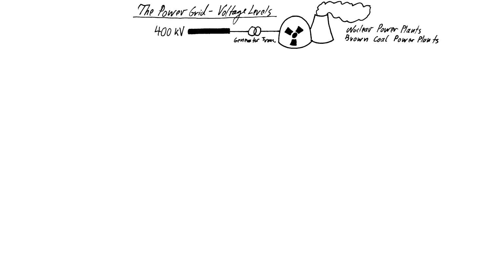Despite recent changes like the advent of renewable energy and of high voltage direct current transmission lines, the power grid still largely remains a three-phase AC system with a hierarchical structure, with the major sources of energy at the top, the industrial consumers in the middle, and the households at the bottom. At the highest level, we have the 400 kilovolt grid that is supplied with electric power from the most powerful power plants in the country. The synchronous generators inside most power plants, however, only deliver a supply voltage between 6 and 30 kilovolts. Therefore, so-called generator transformers have to step up the supply voltage to the 400 kilovolt level.